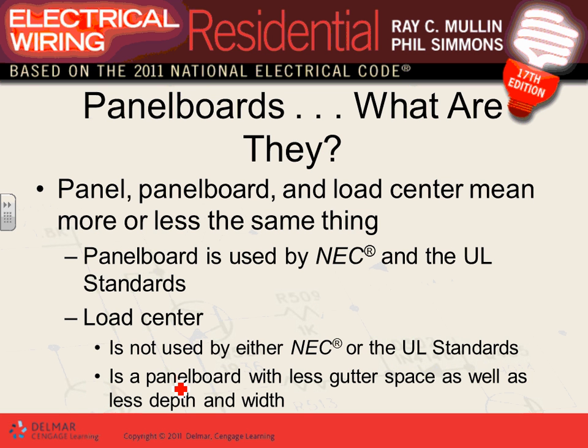There are terms like panel boards and load centers. The NEC calls them panel boards. Load centers are a residential, cheaper alternative to a panel board — they're made to fit between studs at 16 inches on center, and are 3½ inches deep to fit 2×4 lumber framing.